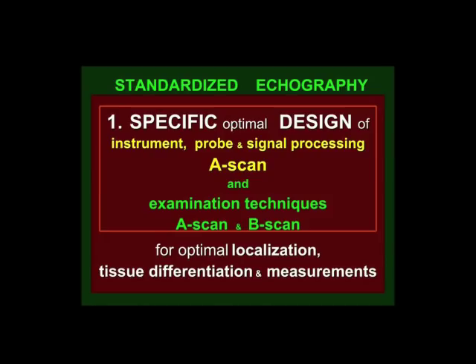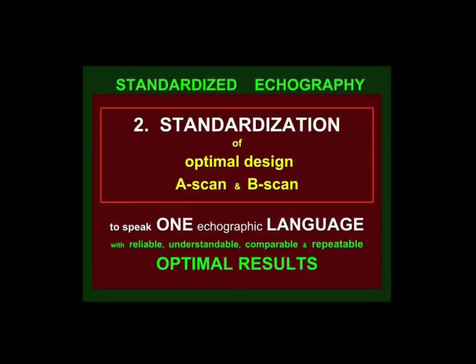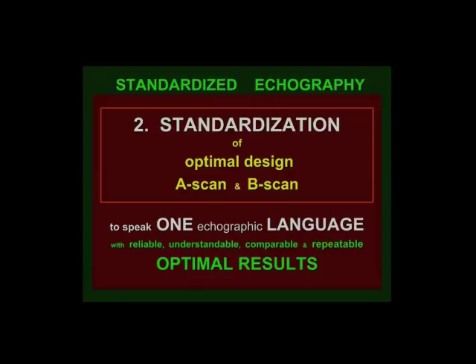This special design is extended towards the examination techniques of both B-scan and A-scan. The special design of the A-scan instrument and the examination techniques involved in standardized echography are standardized — that's where the name comes from. This optimal design is standardized so that we speak one echographic language with reliable, understandable, comparable, and repeatable optimal results.